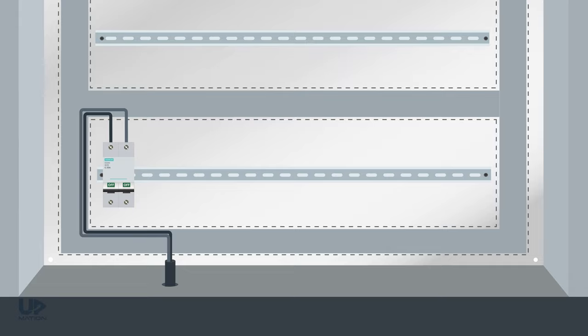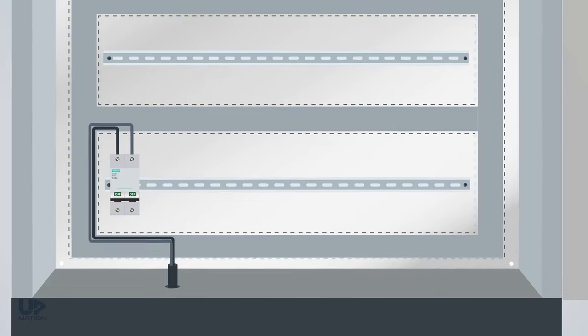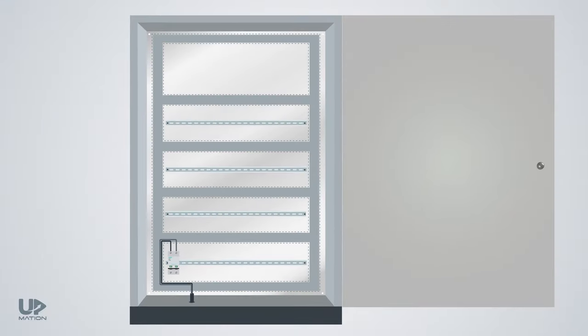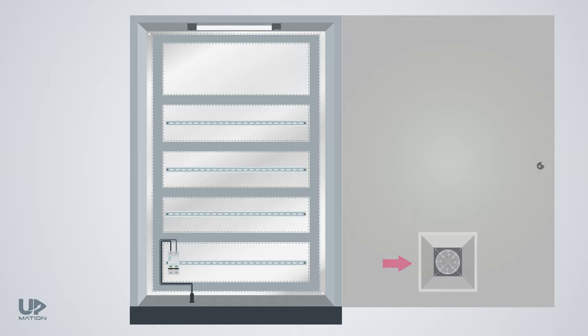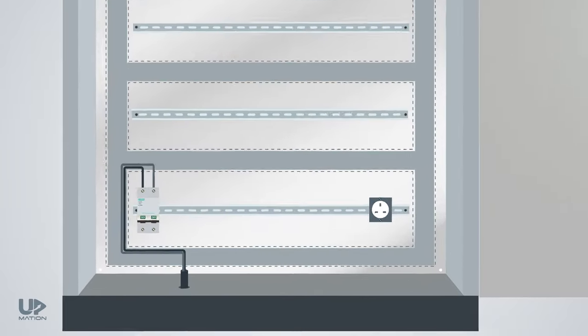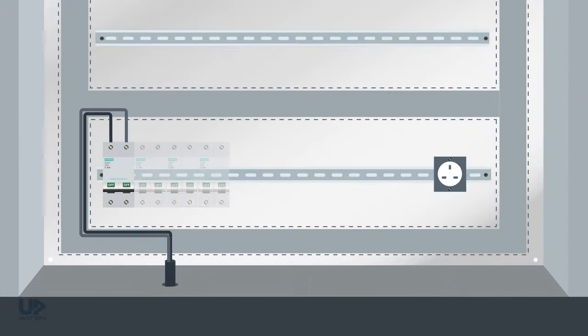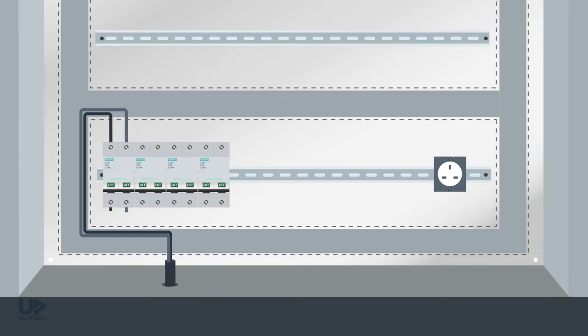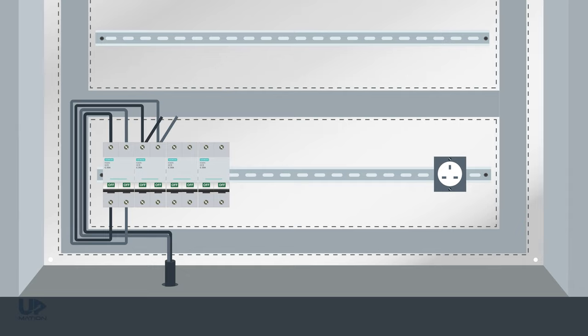Now that we have electric power inside, we should distribute it between different devices. First, we need to supply the utilities of the control panel, like the lamp, fan or heater, and socket. Let's consider a separate MCB for each of these devices. The standard way to connect the wires to an MCB is to connect the input wires to the top side and the output wires to the downside connectors. So I take the power from the main MCB and connect it to the input of the other MCBs.